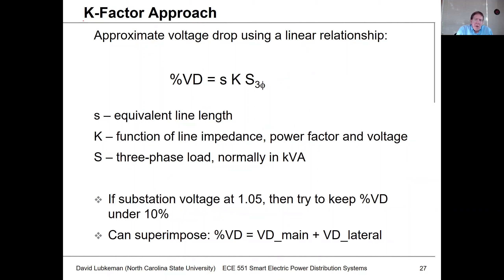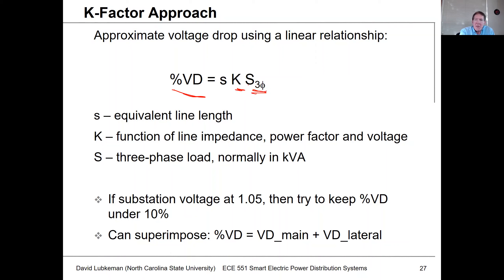This is a linearization where we make certain assumptions about the nature of the voltage drop to come up with simplified ways of doing voltage drop calculations. For this K-factor approach, we calculate a percent voltage drop across a system, which is a function of the K-factor multiplied by the net load KVA multiplied by an equivalent line length. Once you have a given K-factor and an equivalent load, the longer the line, basically the more voltage drop you're going to have, and we assume it's linearly related.